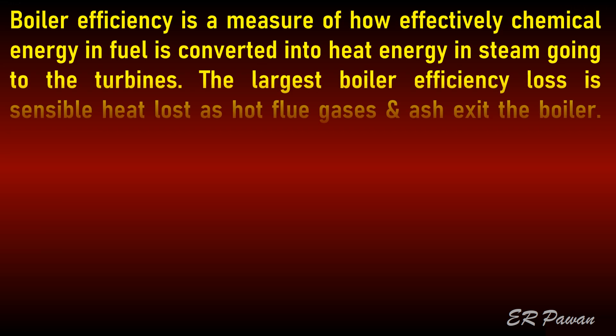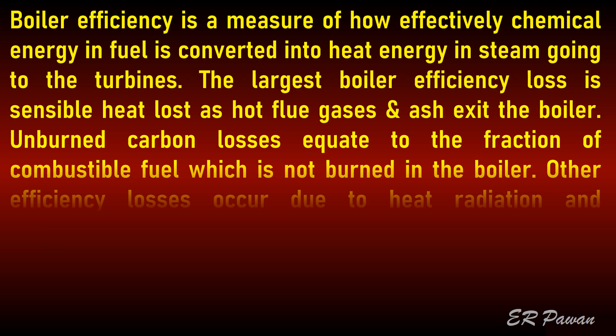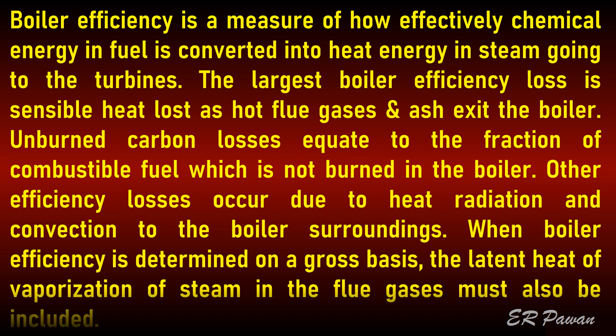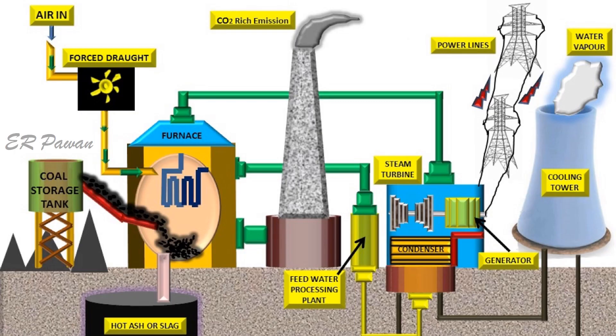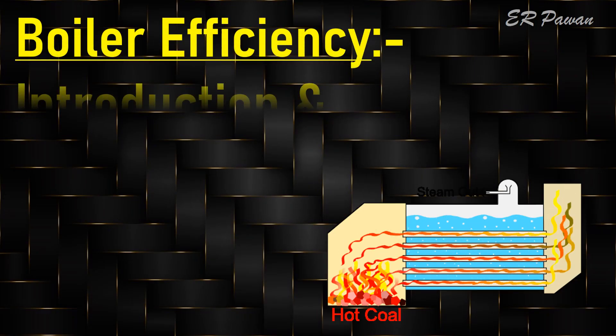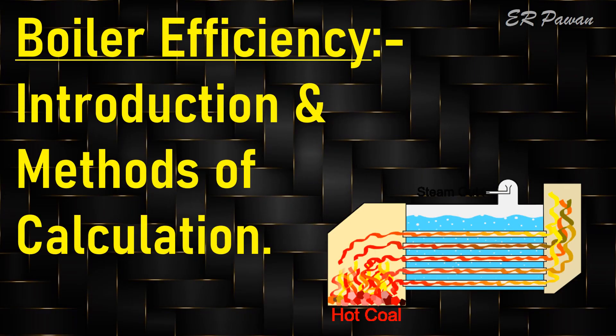Unburned carbon losses equate to the fraction of combustible fuel which is not burned in the boiler. Other efficiency losses occur due to heat radiation and convection to the boiler surroundings. When boiler efficiency is determined on a gross basis, the latent heat of vaporization of steam in the flue gases must also be included. Boiler efficiency: introduction and methods of calculation.